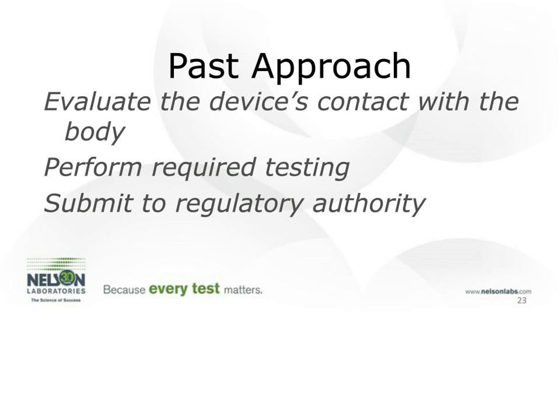But in the previous approach to this chart, a manufacturer would just look at their device, evaluate the contact, and then say, okay, these are the tests I need to do. I hate to use this word nowadays, but it was a checkbox mentality. Okay, there's my test, check, check, check, check, check, and they would do that suite of testing. They would submit it to whatever regulatory authority they were looking to submit to. And then they would sit back and field questions, if there were any, but usually it had to do with maybe some test-specific questions. But you pretty much passed into the regulatory arena with checkboxing those tests.